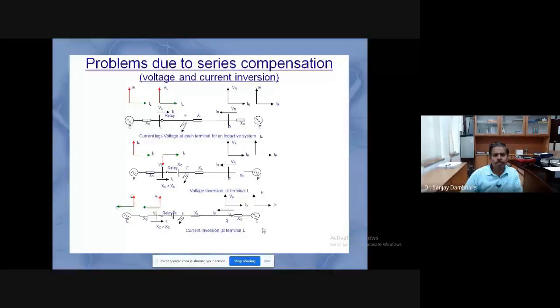This slide shows the effect of compensation. Let's take series compensation, where the line is compensated by a series capacitor like TCSC or similar devices. The transmission line impedance seen by the relay depends on where the fault occurs and what compensation, meaning what capacitor, is present in series.